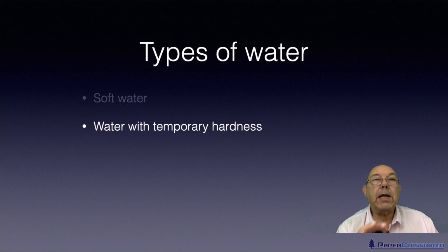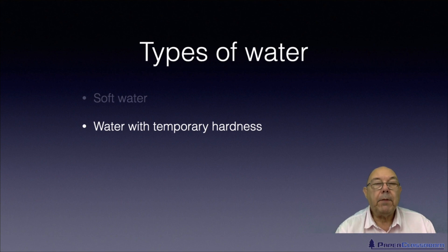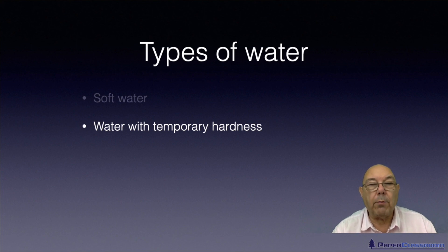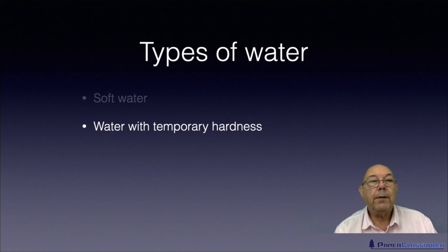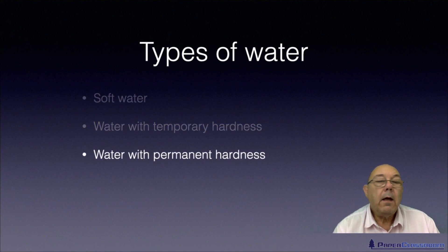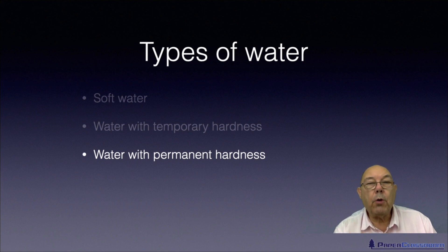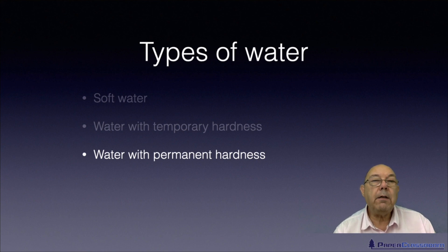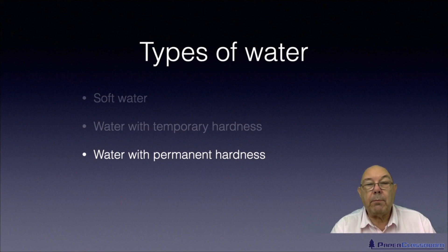You've got water that has temporary hardness — if you boil it, the hardness will disappear. You actually get a deposit of calcium carbonate formed, and once that material is out of solution as an insoluble solid, it's no longer in solution to cause the problems that hardness causes. Then there's water that is permanently hard — no matter how long you boil it, you will not get rid of the hardness. You have to resort to ion exchange methods or chemical precipitation methods.